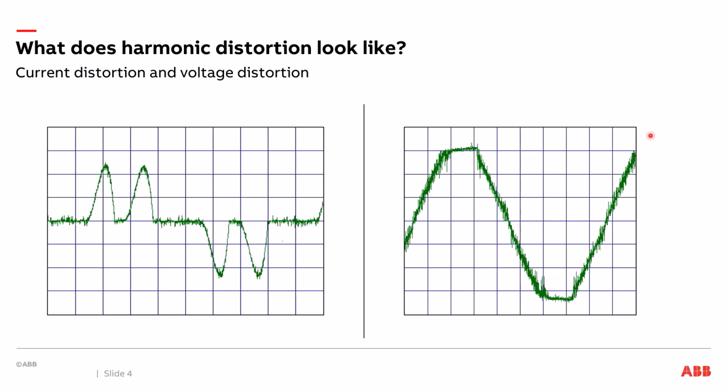So when you talk about harmonics, the percentages get thrown out a lot in order to kind of compare this waveform to another waveform. So just keep in mind, this right here is a little over 5%, which I would consider to be a pretty poor quality waveform in my facility.